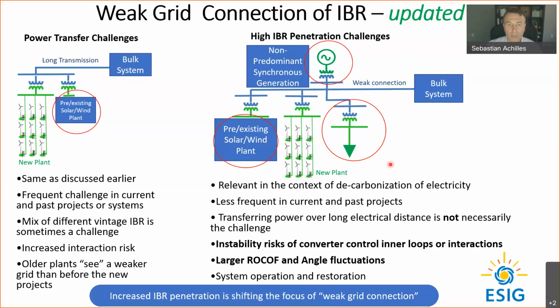I'm purposely defining this problem as not related to a power transfer problem. You could have both problems, but in principle, although you have a weak connection, you're not pushing a lot of power through it. In this case, you have other problems more related to the inner loops of the controls, the converter controls in the different equipment, the old or the new one, that make it unstable because the system is actually very weak. There are more aspects related to frequency, which may have changes that are really fast because you don't have significant synchronous machines. Angle fluctuations in some of the buses in this area could be very significant and cause trips. In addition to that, system restoration could be an issue.